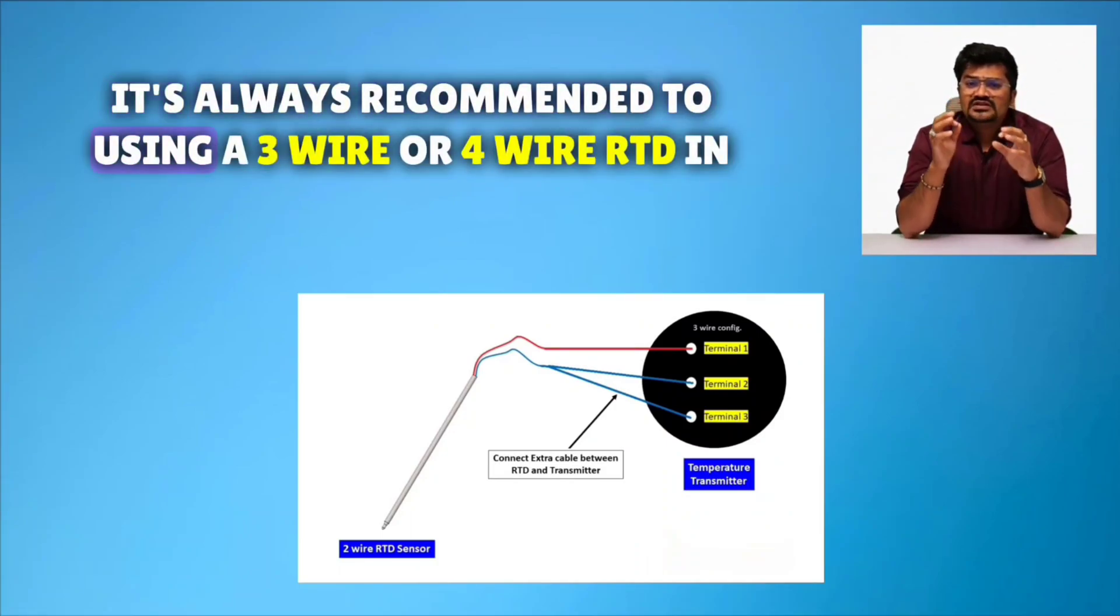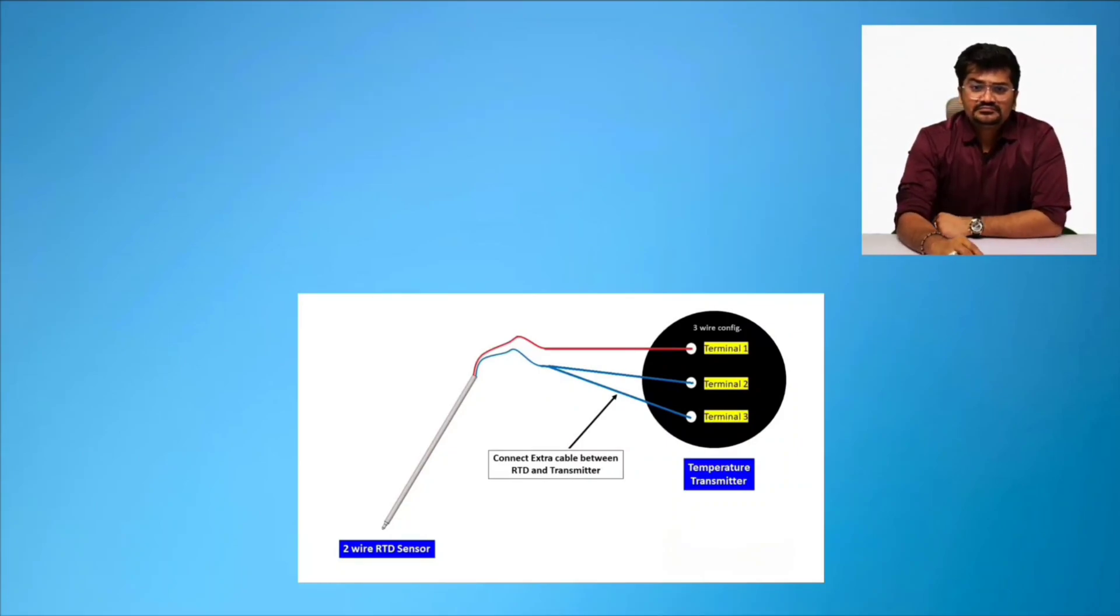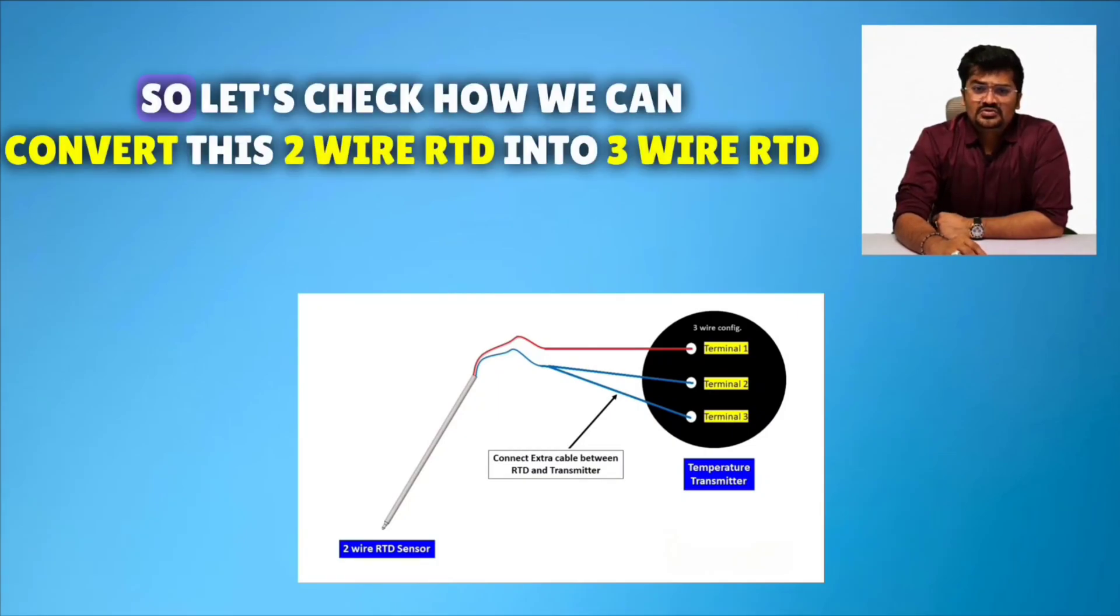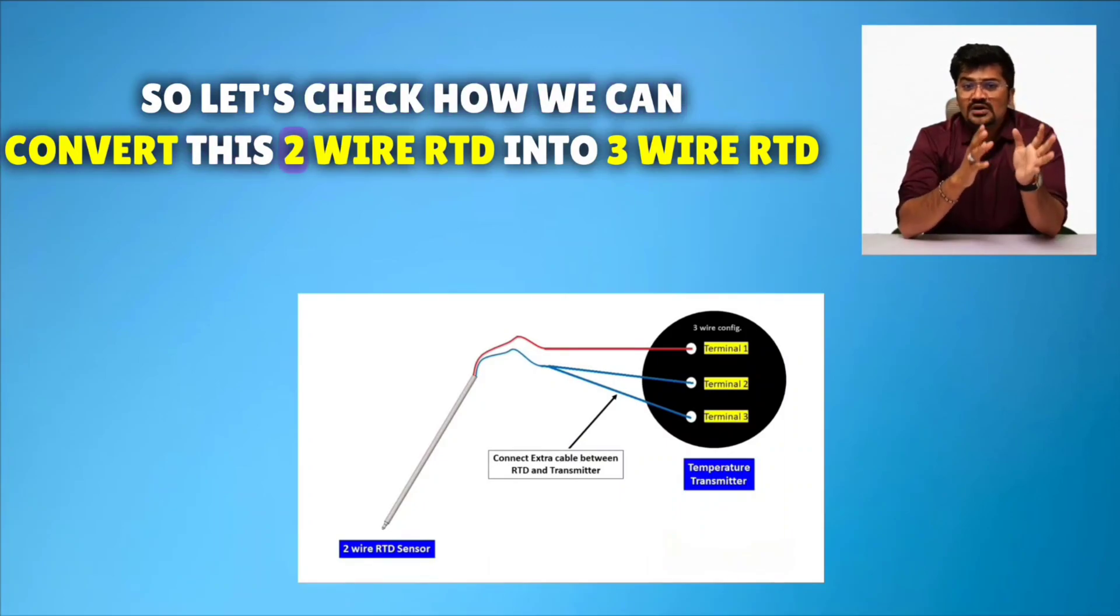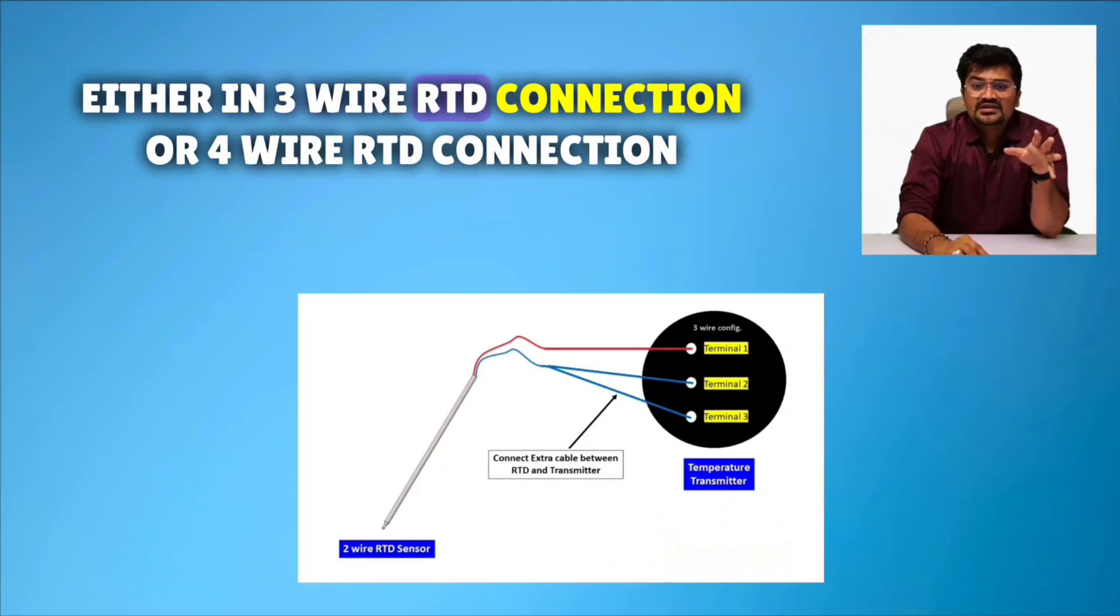It's always recommended to use a 3-wire or 4-wire RTD in this type of situation. Now, we have already 2-wire RTD. So let's check how we can convert this 2-wire RTD into 3-wire. We have to connect 2-wire RTD to the temperature transmitter either in 3-wire RTD connection or 4-wire RTD connection.